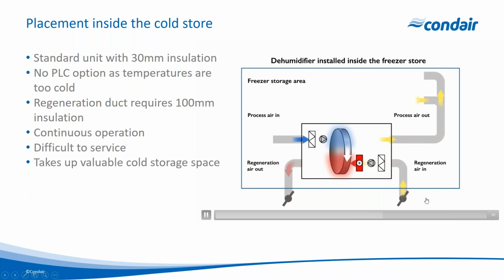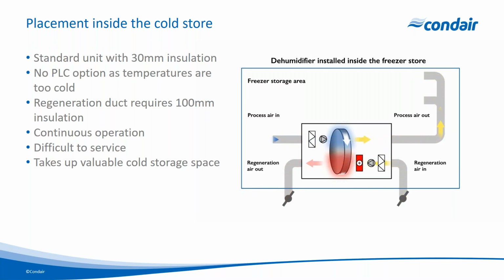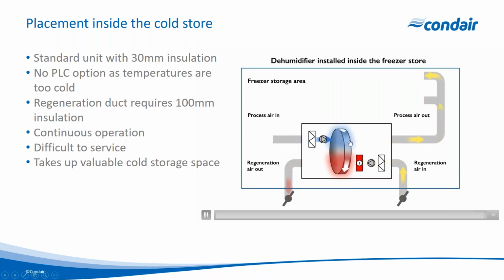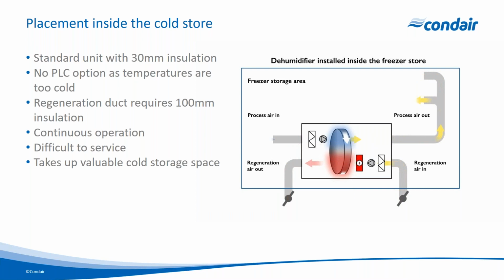But we've got to deal with our regeneration air. So we're taking regeneration air from outside in through a filter, over a fan, then over our heater, then over our desiccant wheel, and then releasing that wet air, that regeneration air being taken out to ambient. Now, this is kind of the traditional aspect of it, but there are some downsides. On the upside, we don't have such a temperature difference between the inside and the outside of the unit, so standard 30mm insulation is all that's needed on the internal side of the dehumidifier. But we can't have a programmable logic controller option here because the temperature is too cold for the PLC. So I can't optimize the system. I can't optimize the fan speeds, the rotor speeds, and the coil. So it becomes less effective, less efficient in its operation.